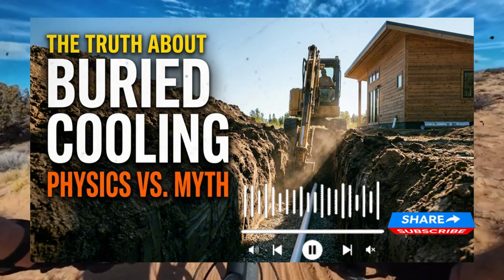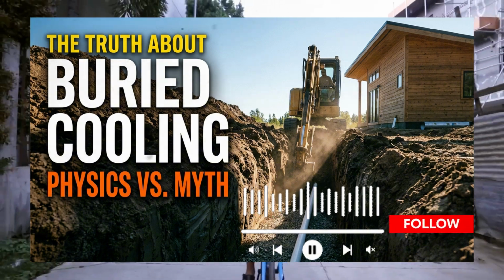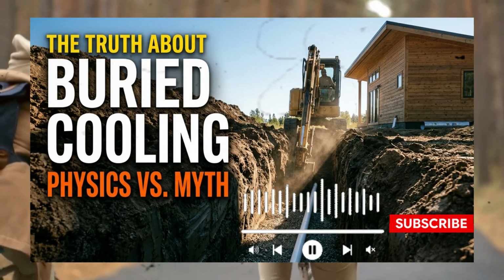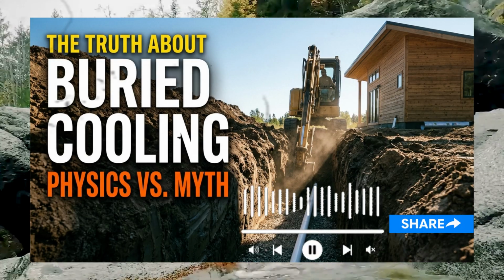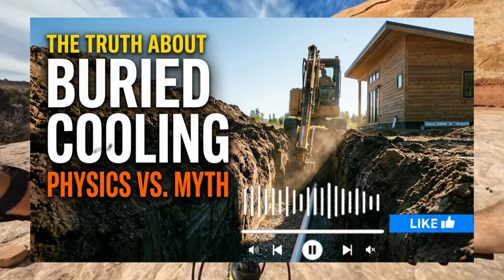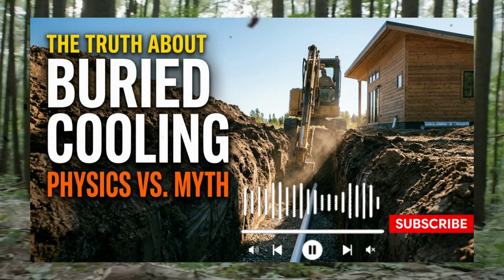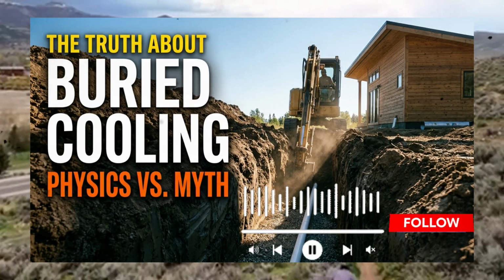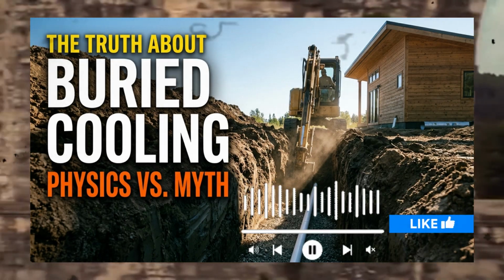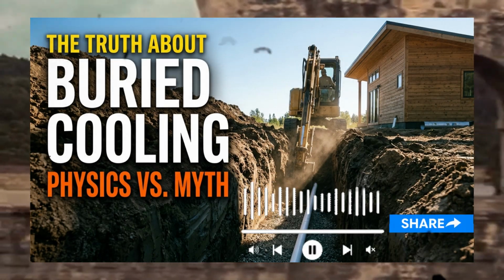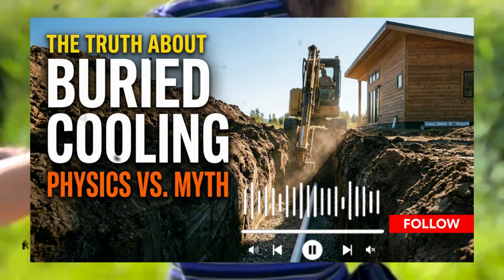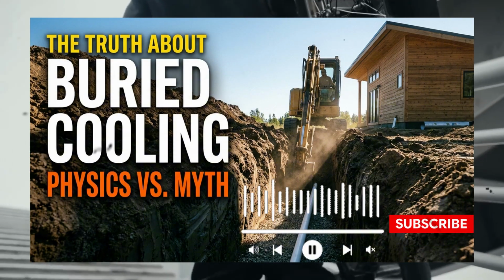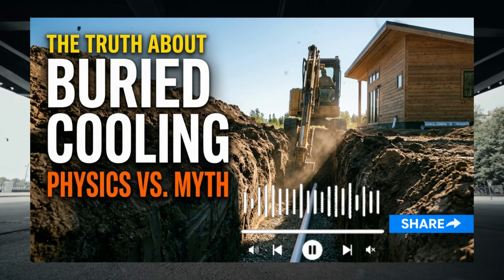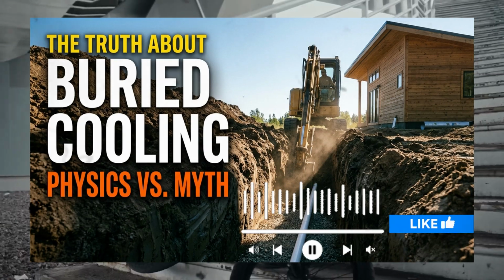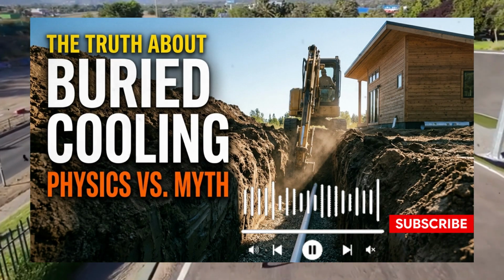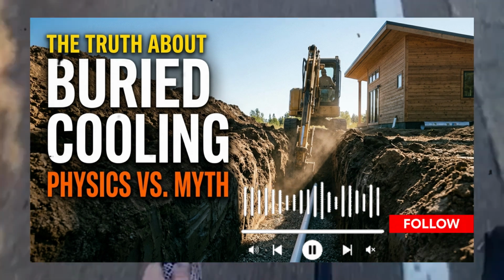living quarters. But here is the critical distinction that we must make at the 16-minute and 30-second mark, a limitation that every responsible off-grid designer must understand. This system cannot lower your indoor space to a chilly 65 degrees Fahrenheit on its own if the solar heat load on your roof is massive. It is not an active, closed-loop refrigerant cycle. It does not possess a thermostat that you can simply turn down to a precise digit.